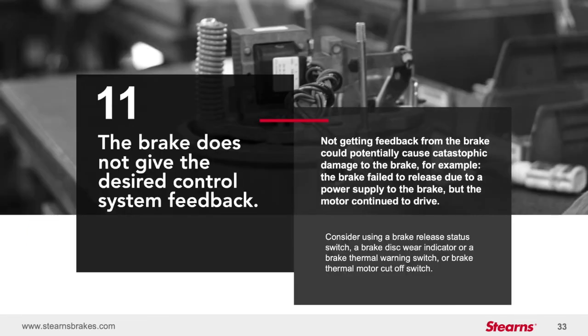The last mistake we will cover today, the brake does not give the desired control system feedback. What we're really talking about here is the decision to use or the lack of awareness of the switches that are available to send feedback from the brake. There are a variety of brake release status switches, brake disc wear switches, and thermal indicators that can be used to send critical feedback from your brake to your control system. You can always check with the brake manufacturer on their options for feedback switches.